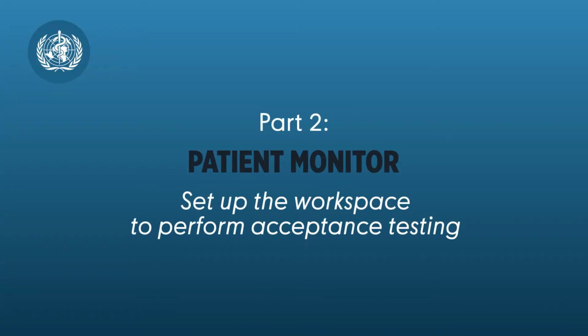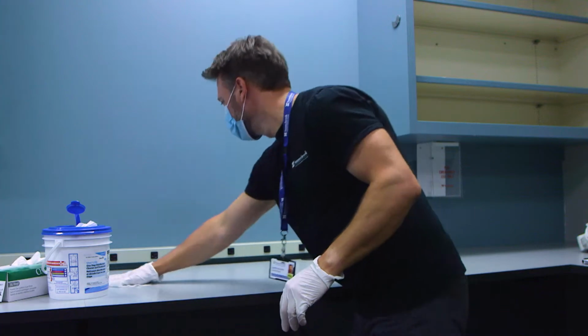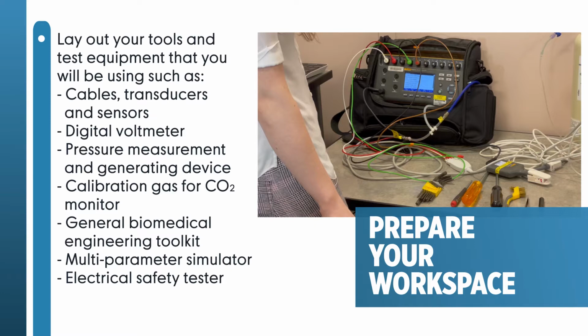Before you start acceptance testing, prepare your workspace. You may be working in an engineering workshop or somewhere else in your facility. Prepare your workspace by cleaning the work area, laying out your tools, and test equipment that you will be using, such as any and all patient monitor accessories, such as cables, transducers, sensors, and others, digital voltmeter, pressure measurement and generating device, calibration gas for carbon dioxide monitor, thermometer and bath, and general biomedical engineering toolkit. If available, a multi-parameter simulator and electrical safety tester are also valuable test devices.